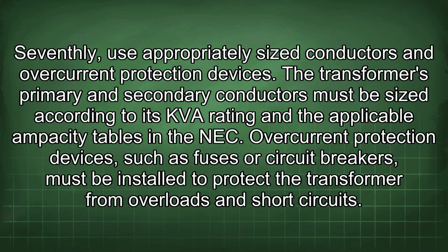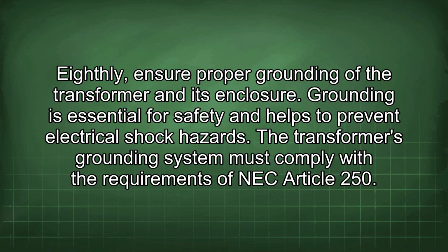Seventhly, use appropriately sized conductors and overcurrent protection devices. The transformer's primary and secondary conductors must be sized according to its kVA rating and the applicable ampacity tables in the NEC. Overcurrent protection devices, such as fuses or circuit breakers, must be installed to protect the transformer from overloads and short circuits. Eighthly, ensure proper grounding of the transformer and its enclosure. Grounding is essential for safety and helps to prevent electrical shock hazards. The transformer's grounding system must comply with the requirements of NEC Article 250.